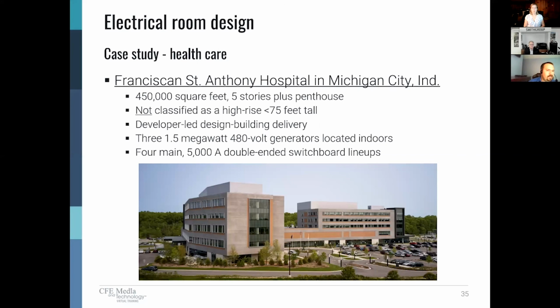This was a developer-led design build delivery model for the project. The building had 3 1.5 megawatt 480 volt generators located interior to the building, and had 4 main 5,000 amp double-ended switchgear lineups. So we had some big equipment in here. Next slide, please.